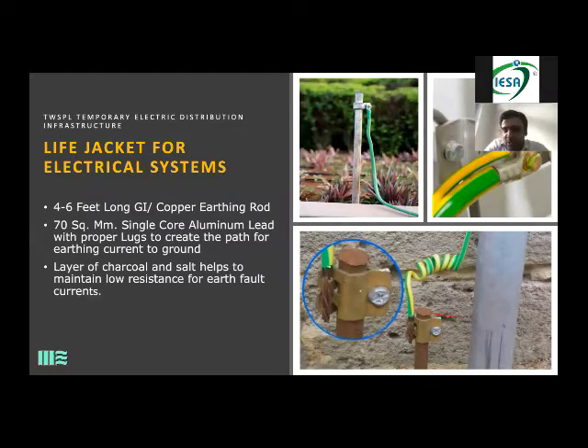Okay. And then we've got another question from Sarabjit ji. Is one good body earth for a hanger sufficient? What is the quantity, and does it depend on the size? So one good body earth for the hanger is absolutely fine. If you have a huge hanger, maybe an 80-meter hanger, then maybe on one side and on the other side also. Because by the end of it, your hanger is interlinked. When you do earthing on one point, it automatically reaches the end point also. But if your hanger span is longer, then it is suggested that you do two body earths, just to be on the safer side.